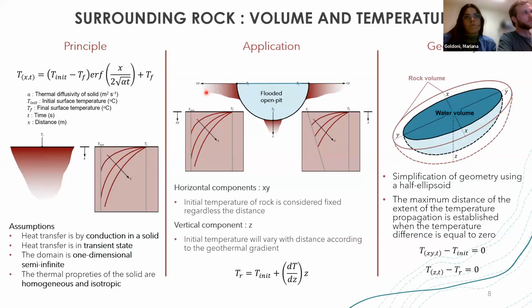The volume and temperature of the surrounding rock are more difficult parameters to determine. To do this, I use a formula that characterizes heat transfer by conduction in a solid in a one-dimensional semi-infinite domain in transient state. The principle is to evaluate the propagation of temperature in a solid over time if there is a sudden change in the temperature condition imposed at its surface. To apply this to characterize heat transfer from water to rock, the distance of temperature propagation must be determined for each axis of the open pit, since the initial temperature acts as a boundary condition and varies with the spatial component of the geometry.